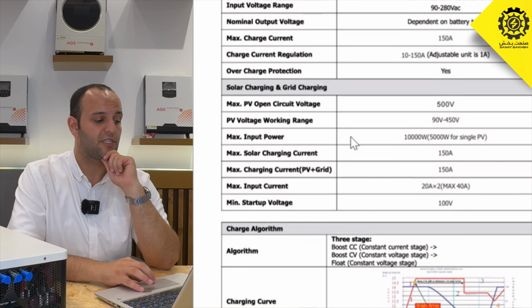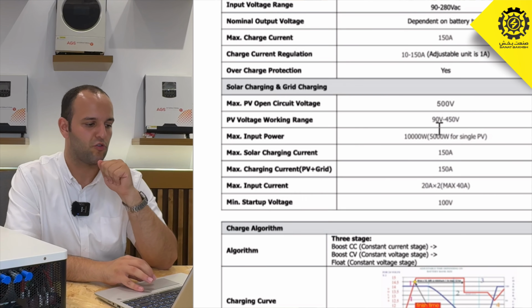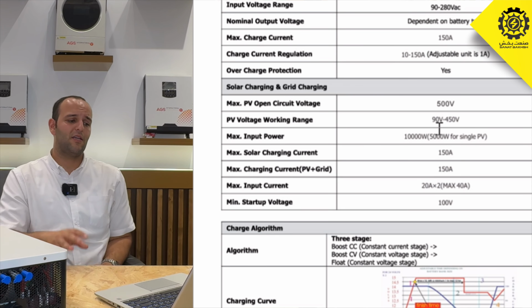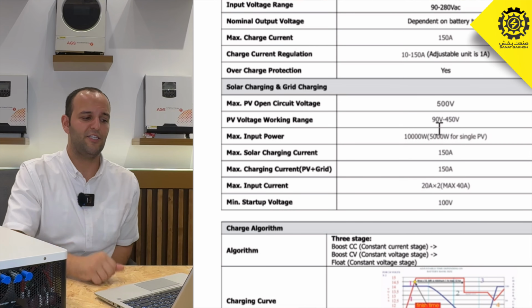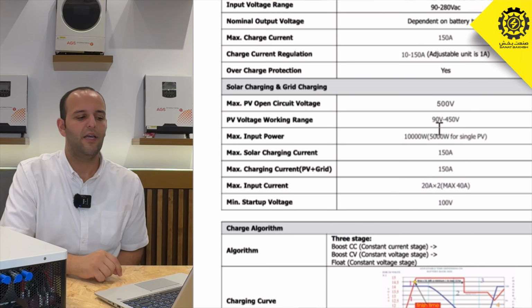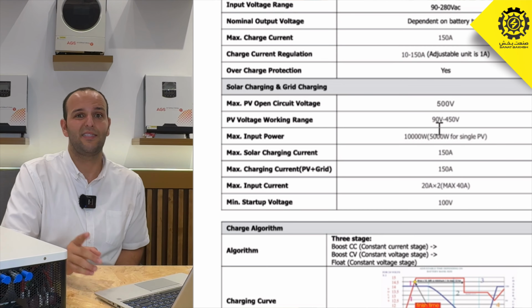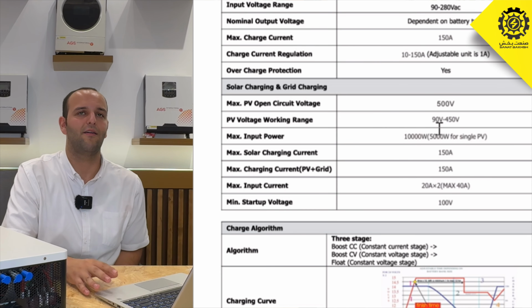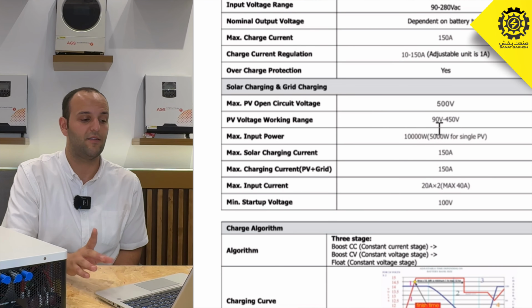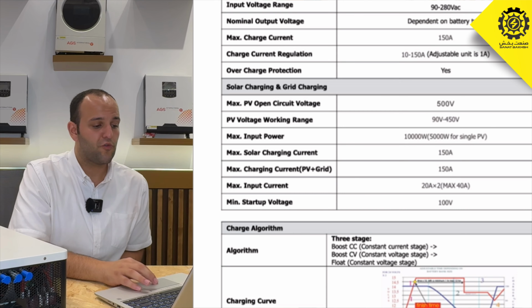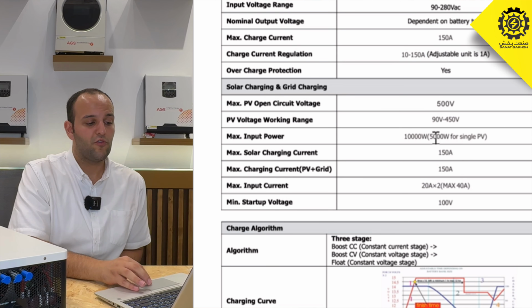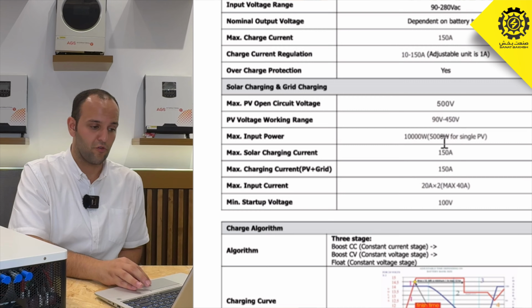Solar charging and grid charging. Max PV open circuit voltage is 500 volts. It's very good if you want to connect all the solar panels in series. Each solar panel is 48 volts. If you connect 10 solar panels in series, you will have 480 volts. PV voltage working range is 90 volts until 450 volts.